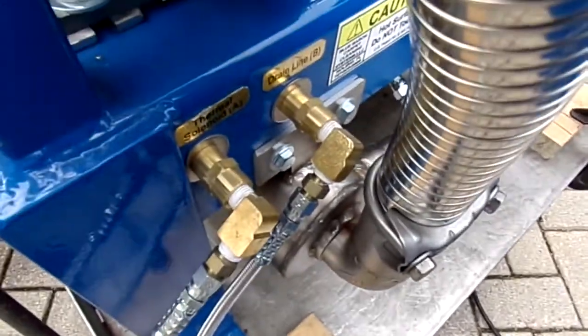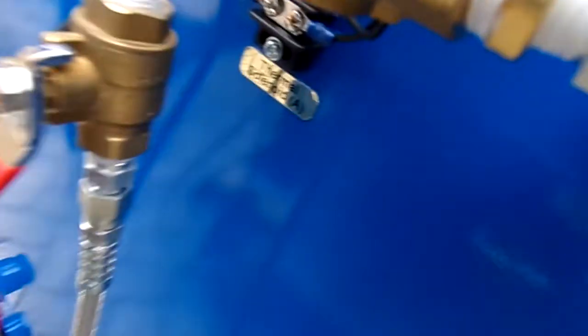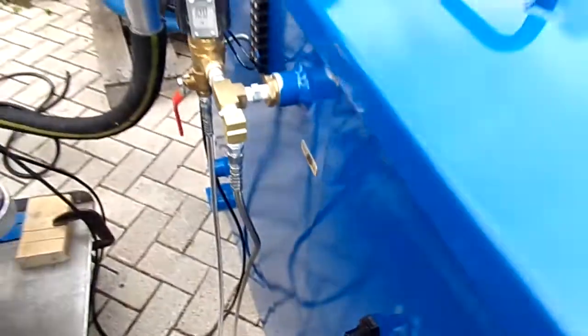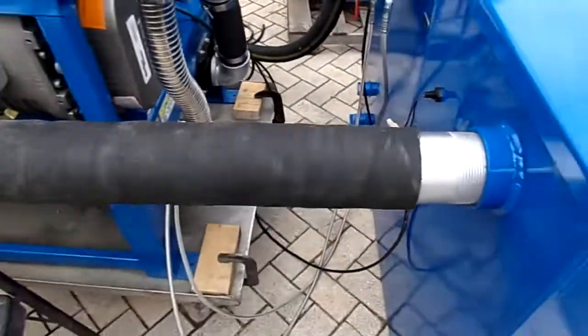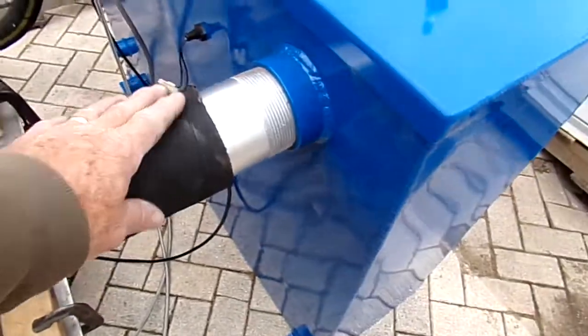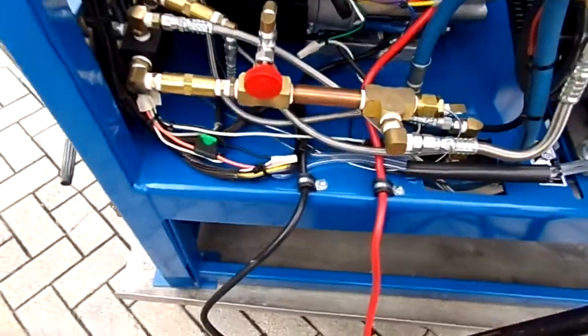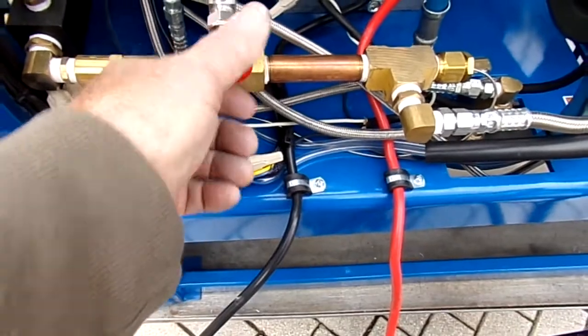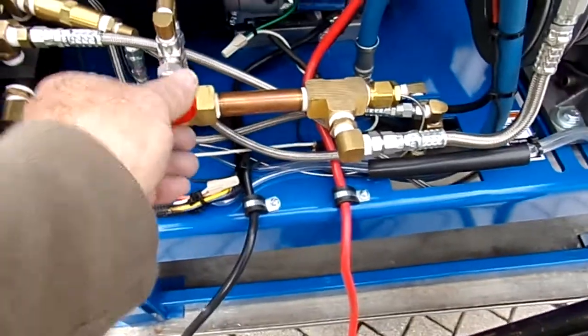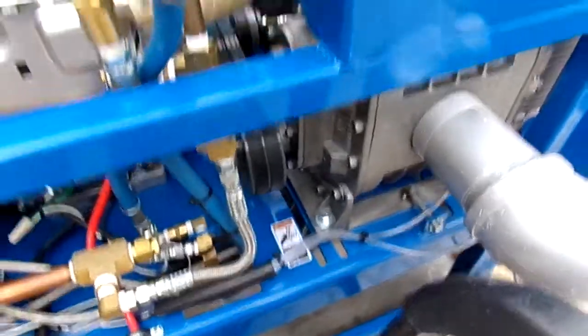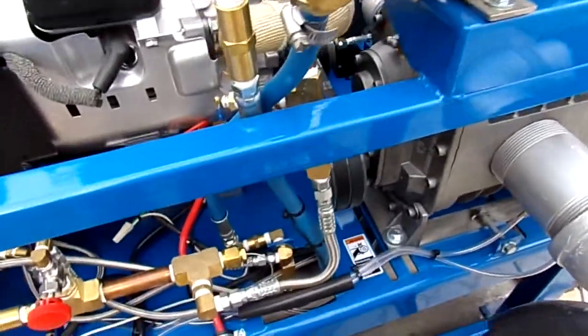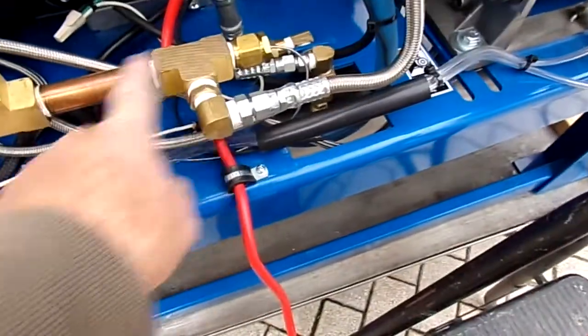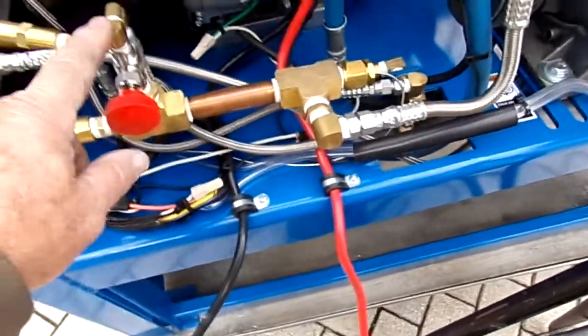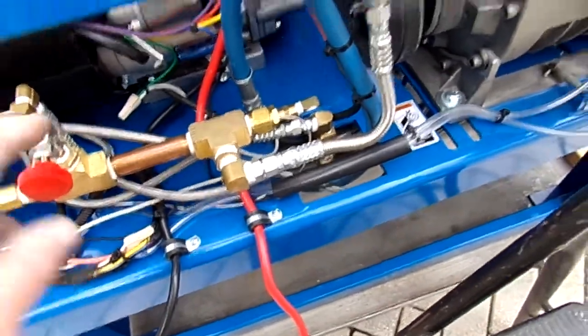Everything's connected, drain B to drain B, thermal A to thermal A there for these stainless braided hoses. You got your vacuum relief, everything's connected. Your interconnect hose, which is a 3.5 hard wall hose connected straight in. Here is a relief valve, needle valve, that actually should be cracked a little bit, enough to allow movement of your temperatures so that you get real-time readings, and this thermal capillary will react better. As you can see, it's downstream, so it'll react better and more efficiently.